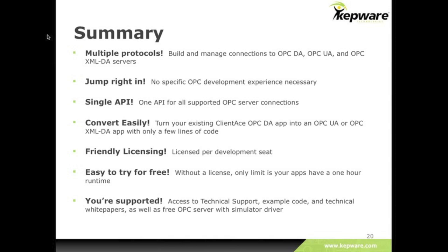With XML-DA, unfortunately, there's not really. So just to reiterate what I said before, I'm going to slow down a little bit. Fault tolerance in OPC DA is lacking in that protocol itself. So it's up to third-party products to provide that kind of failover between target OPC DA servers. So what ClientAce can do is leverage those third-party products. Like our product would be redundancy master, and we would be able to fail between server pairs in order to provide fault tolerance for your OPC DA connectivity. XML-DA and our UA connectivity are limited by the implementation of UA. So there's not fault tolerance built into those kinds of connections.